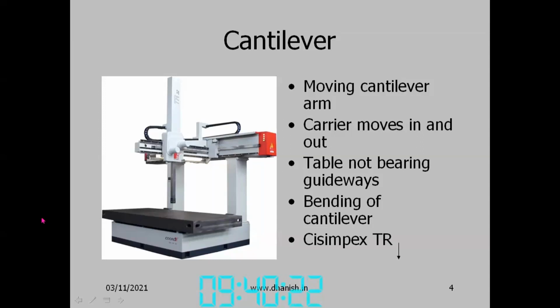The accuracy gets reduced because of this bending. If it is always the same weight, it is okay, but when we change the stylus, etc., we change the weight, and all that results in uncertainty in the measured coordinates. The systematic error may be changing.